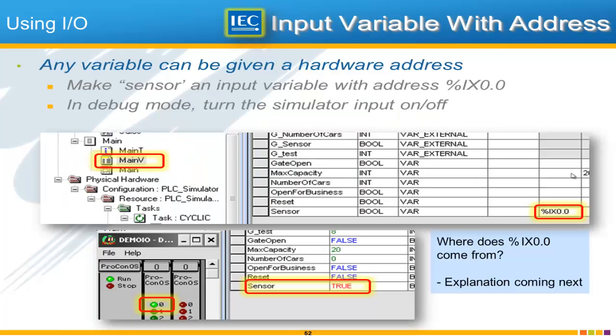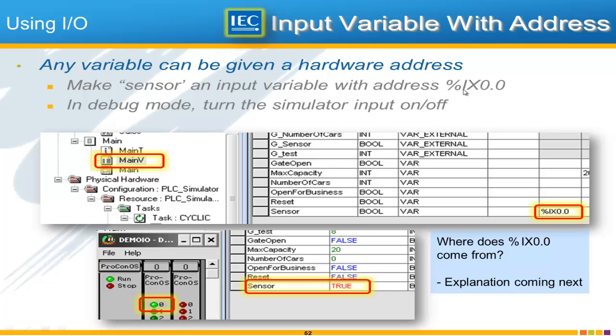And so without getting into any more of the specifics I will just tell you that this input 0 is already configured in the system as address %i for input and x0.0. And all you have to do to turn a variable into an input variable basically to make that tie between a physical input and a variable is to give it an address in the address column.